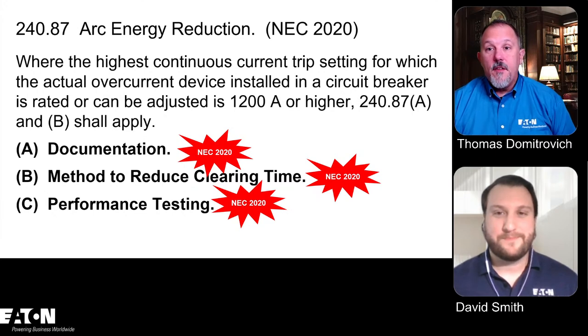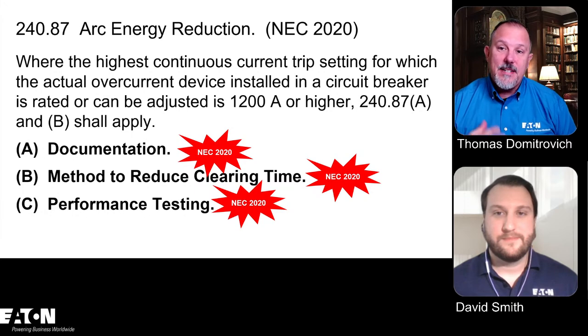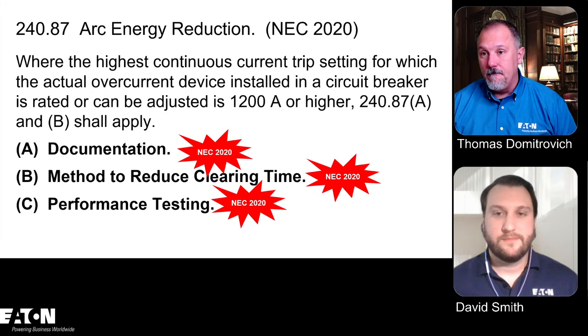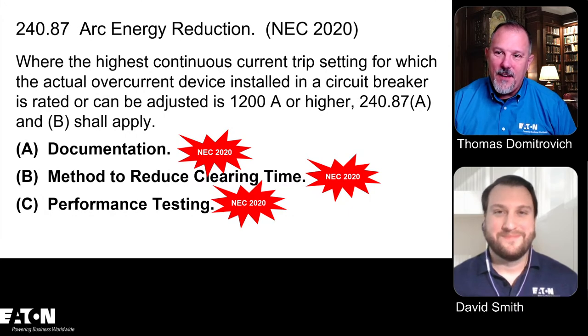Okay, so where the highest continuous current trip setting for which the actual overcurrent device installed in a circuit breaker is rated or can be adjusted is 1200 amps or higher. This text drives a lot of debate, and you haven't even gotten out of the first sentence.